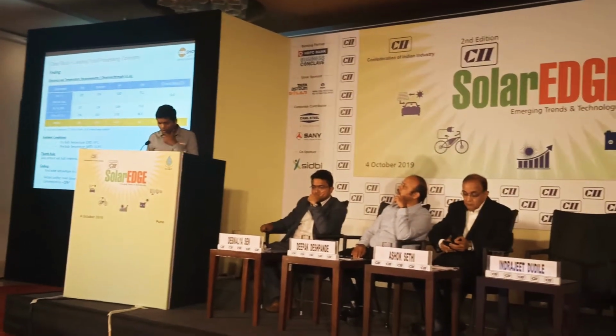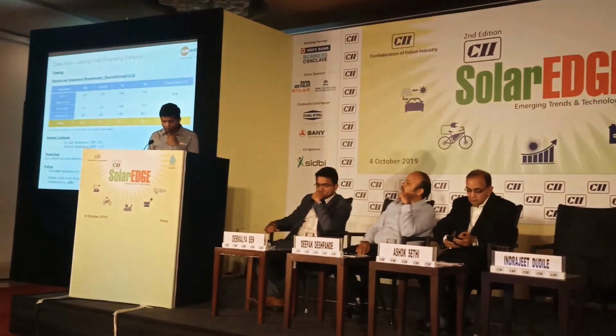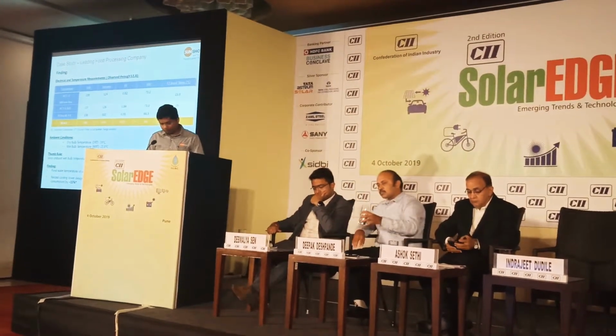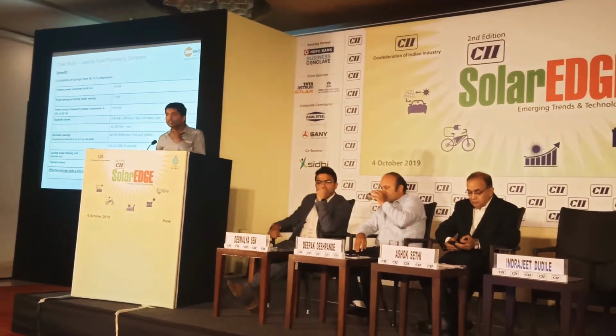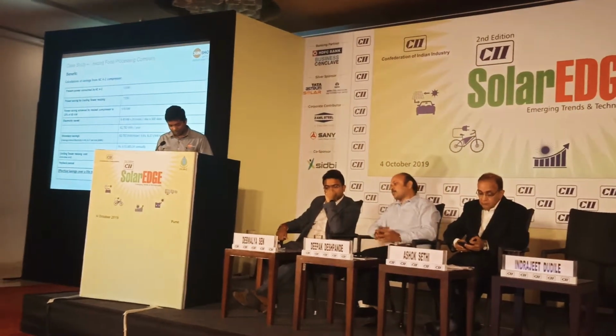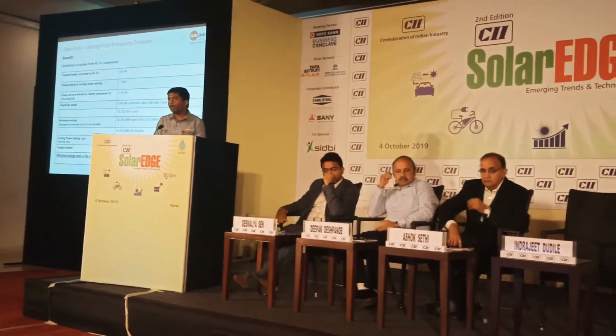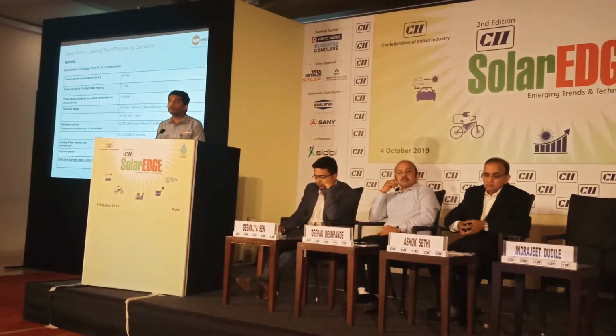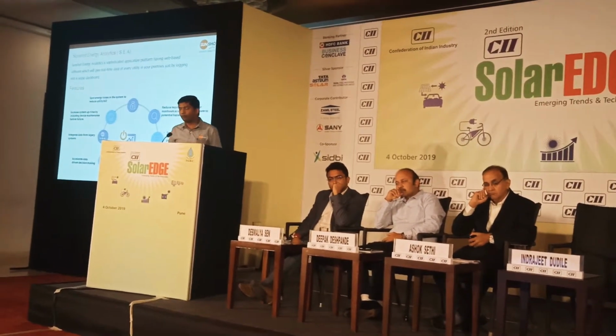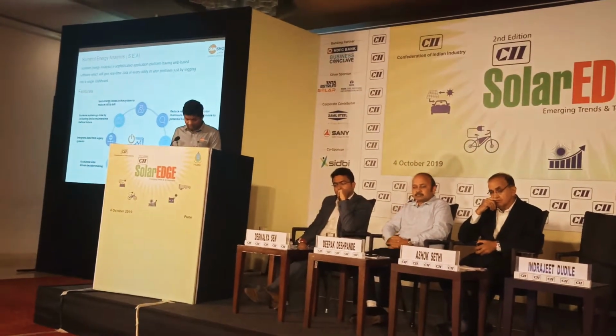So we saw that the ambient temperature was higher at the cooling pond of one of the chillers, and resizing was required. The client worked it out and said, we have a 3-year payback for this particular initiative, but after payback, given the life of the cooling tower, we are going to have enormous savings. This was just one case that came up after installing the energy analytics platform and seeing how the benefits can come up. As we go forward, we'll have more and more such cases driven by the data, and the client will be able to benefit from it.